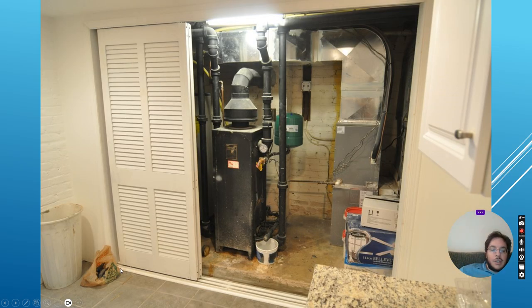And then if we've got a utility room, the utility room needs its own circuit, and the furnace needs its own circuit. And then if you've got a hot water tank, that needs its own circuit. And some people are going with inline tankless systems, and the tankless systems need their own circuit, and it could be very big. So you want to match the ampacity of the tankless circuit to whatever system you're getting. And I've seen in some houses, for example, they have a gas-fired hot water system, but they still rough in wiring for a potential tankless system later, just in case, because you don't know, and it's better to just have it and plug it in when you need it. Doesn't really cost that much to put it in. Although gas is better, a lot of times, hey, you're not gonna have capacity in your panel these days to put all these things, the electric tankless and then the car charger and then the air conditioner. It can add up pretty quickly.